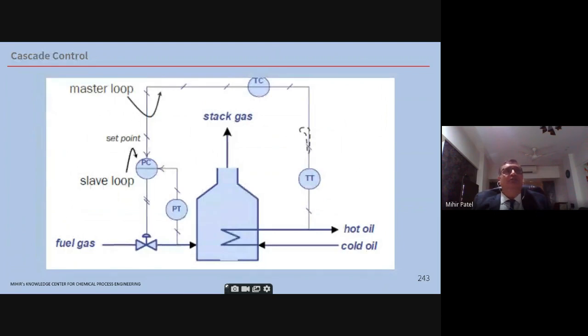Cascade control. Here you see the fundamental control is the pressure of the fuel gas going into the fired heater. Okay. The slave loop is the pressure controller of the fuel gas. The final control you want is the hot oil temperature leaving the fired heater. That is the final, desired control. So the temperature transmitter is the master controller, sending a signal to the slave controller. If the temperature of the hot oil goes up, it will send a signal to reduce the pressure of fuel gas, so the fuel gas valve closes. This is a cascade control.